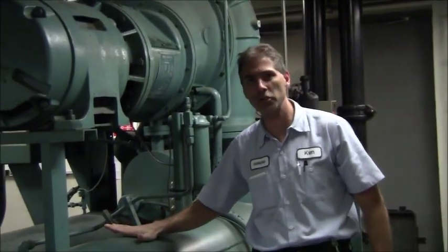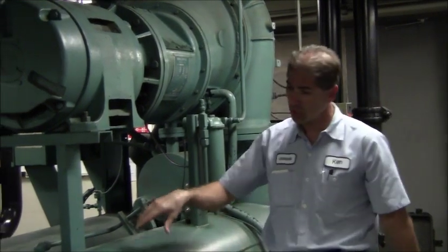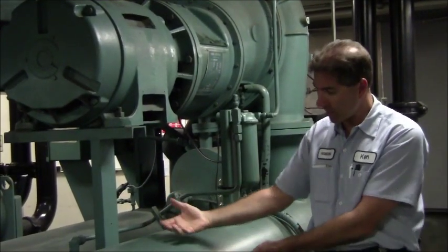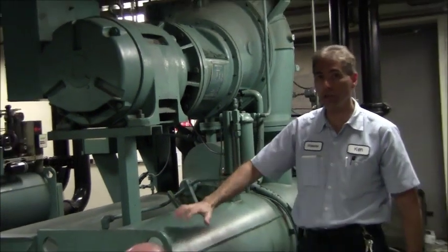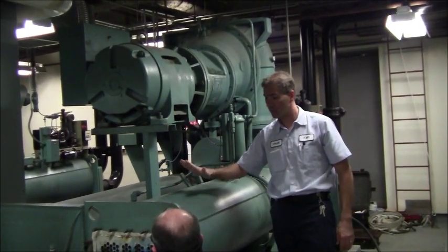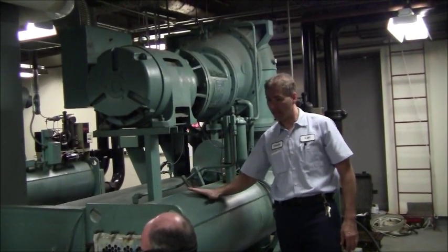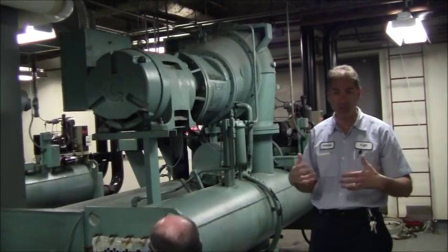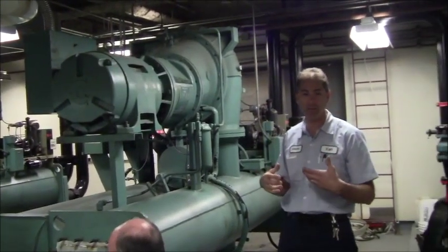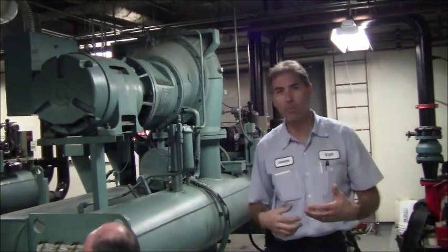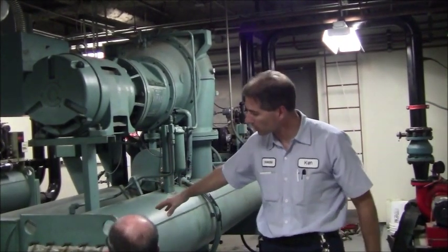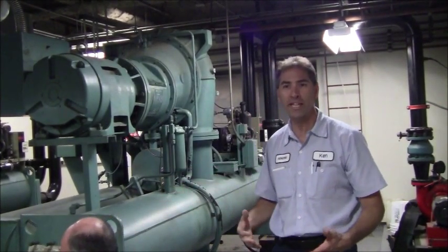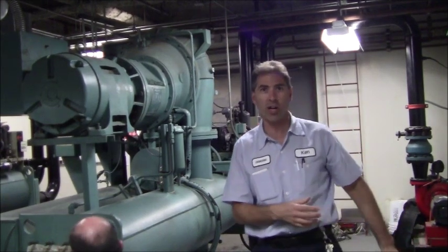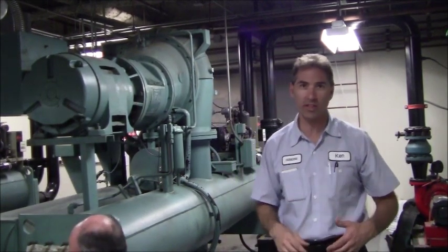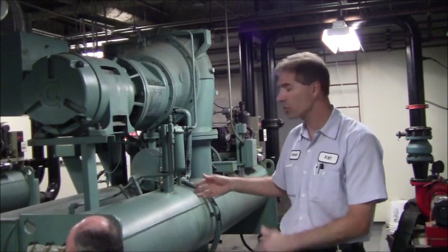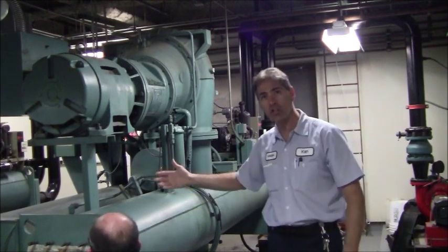So these are shell and tube heat exchangers. You've got tubes and it's just surrounded by a shell. Inside the tubes in this one here is condensing water. And you can build up some type of calcium, magnesium deposits and things of this nature on the tubes. You want to keep your tubes clean, so you have water treatment that goes on to make sure you've got the right chemicals in there. And then due to the age, we're concerned about how long these tubes are going to last.